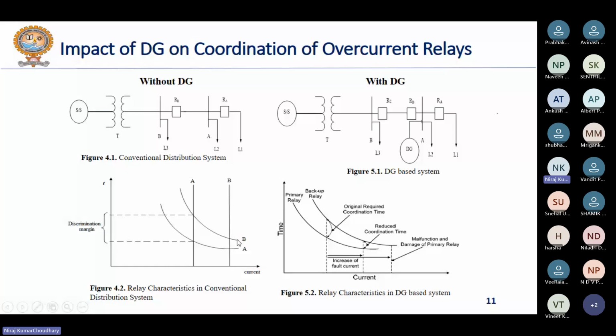Another important thing is that all the coordination between any protective devices should be defined for a particular range of fault current, that is, the minimum and maximum level of fault current. Here the lines A and B represent the minimum and maximum fault current that may occur in this system. The magnitude of minimum and maximum fault current depends upon the system configuration as well as the type of fault. So first of all, you need to determine these two fault current ranges, and only after that can you define your relay coordination problem. So the time of operation of the primary relay should always be lesser than that of the backup relay, and there should be a discrimination time margin between the operation of these two relays.